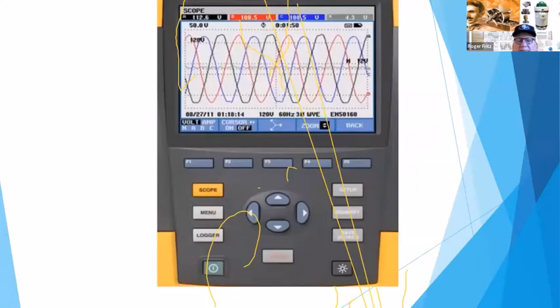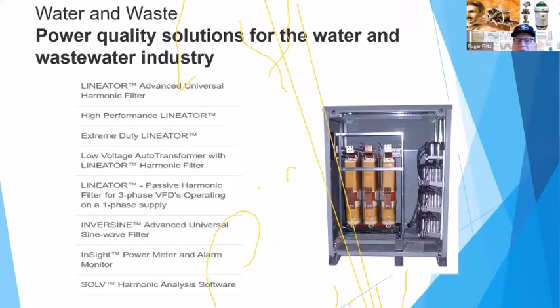So from that, once you start seeing these values, it's also important to understand the effect. So there are various devices out there, different types of what they call harmonic filters, both for the front end side and the back end side of those drive components, which are basically built up with coils, which is basically an inductor, and they put it on all three phases.